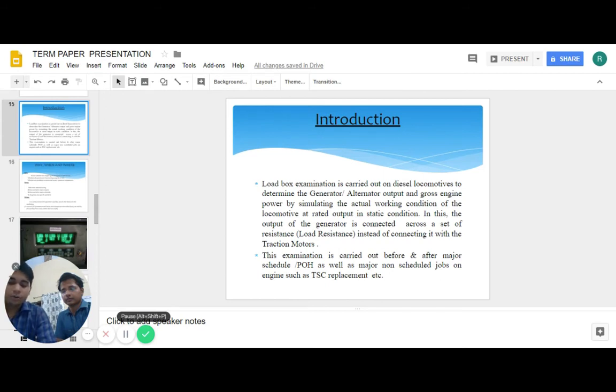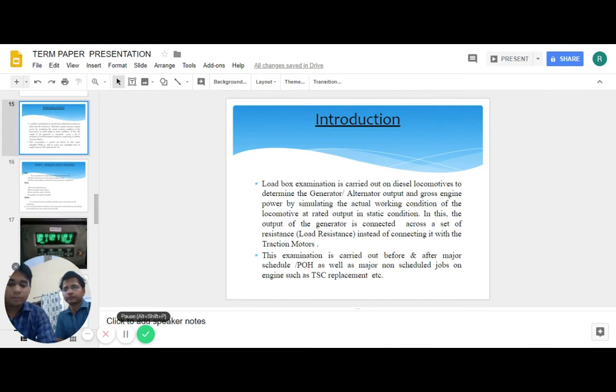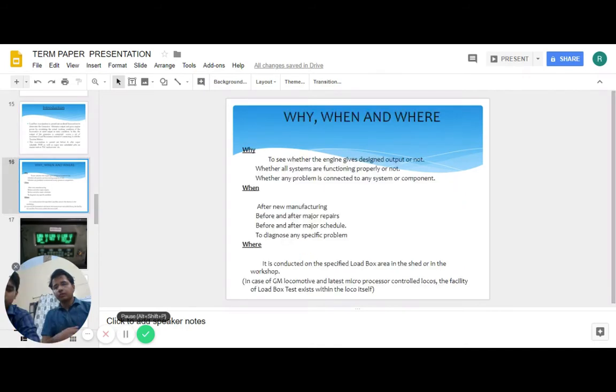During load box test, the output of the engine is measured in terms of electrical parameters, volt and ampere. The output of the generator is connected across a set of resistances instead of traction motor. The output of the engine is dissipated in terms of heat across the resistance.